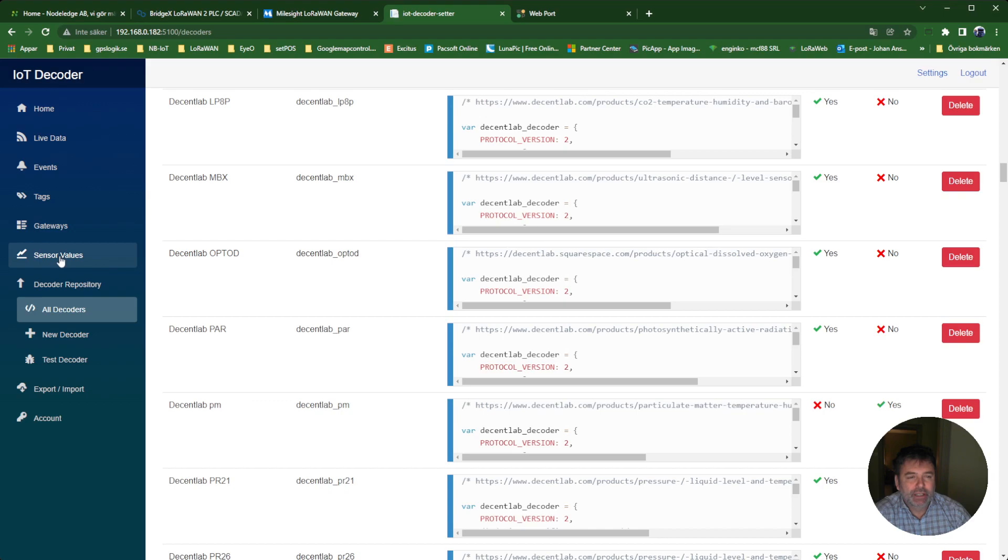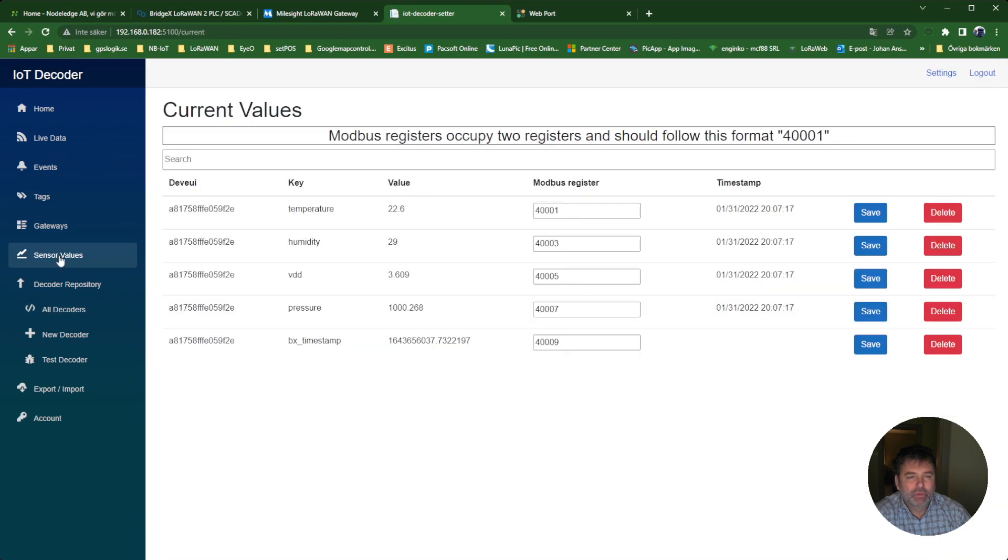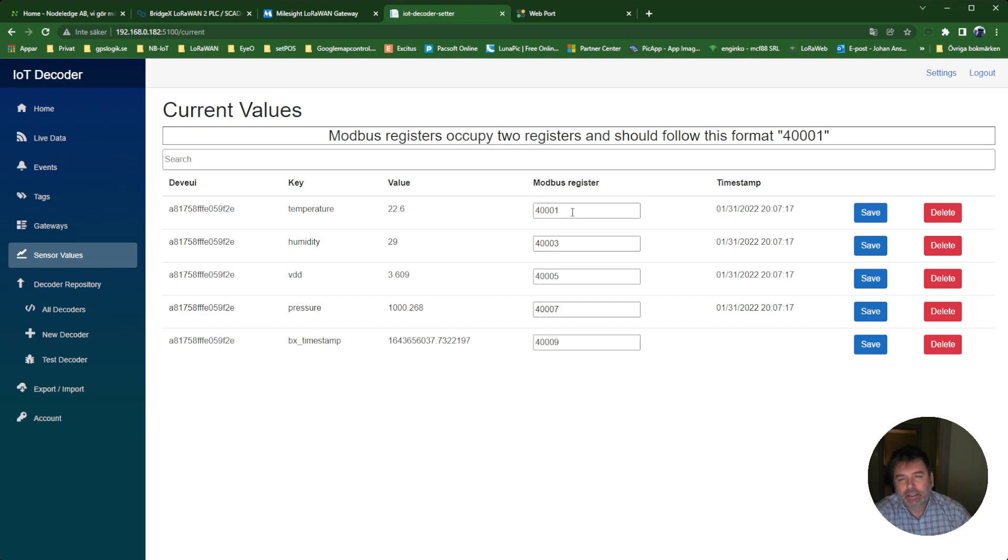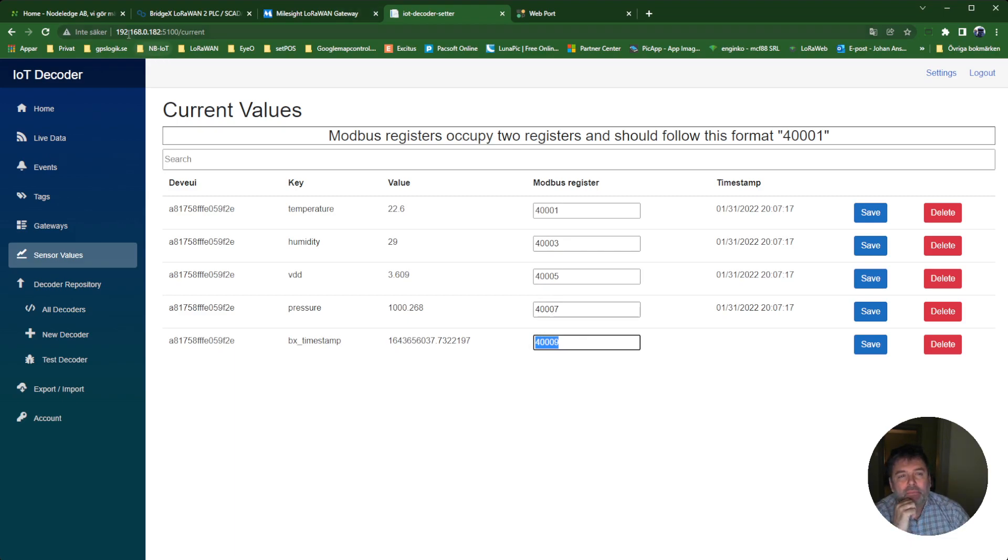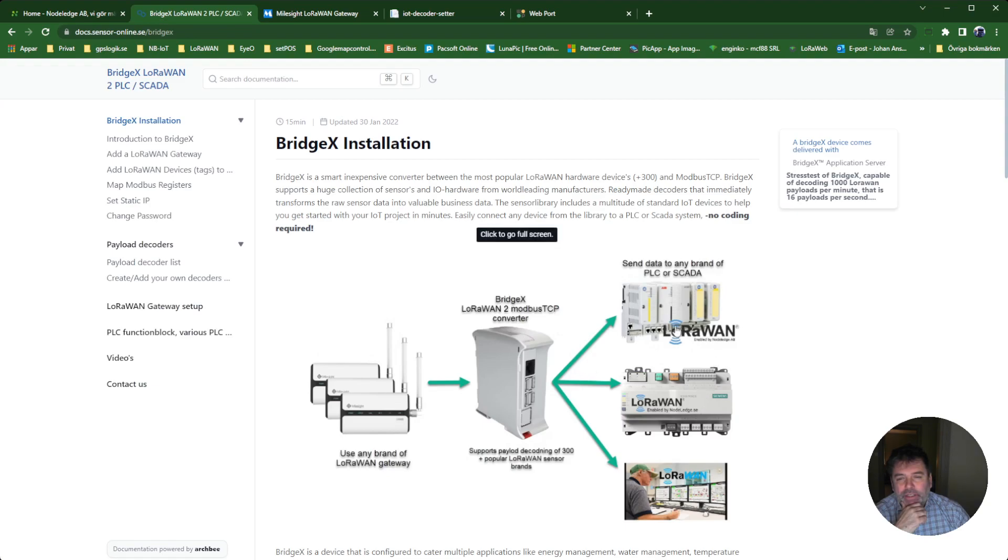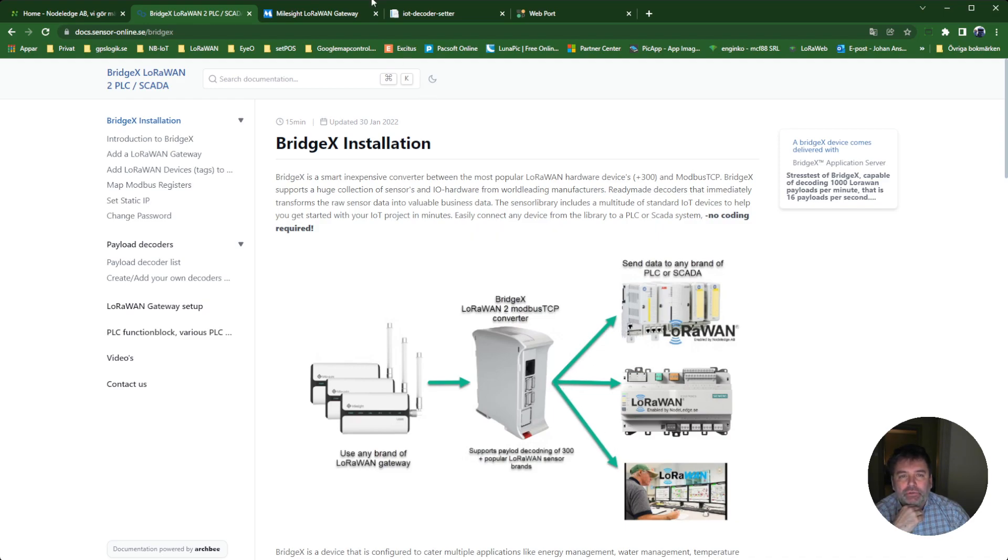If I then go into Sensor Values here, I can see that I have a sensor. It reports temperature, humidity, battery, and air pressure. Here I can set a Modbus register. This Modbus register can be accessed over this IP number of the BridgeX device on port 502. The PLC or SCADA system is going to connect to this device on port 502.